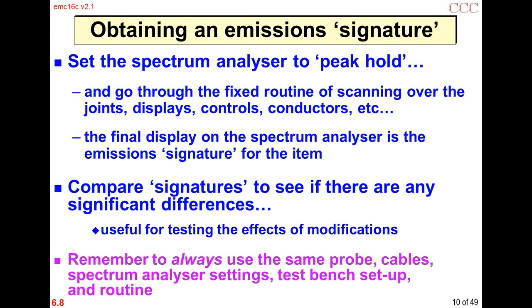But it's very important to always use exactly the same probe. And if you've dinged it, then it's no good. You've got to go get your signature again, because putting a bend in it or something will affect its performance. The same cables, the same spectrum analyzer, the same test bench setup, and of course the same procedure. It helps also to have a particular known source of noise, like your laptop, for instance. You might find that in a particular area of the touch pad, you can see noise on your close field probe, and so it's worthwhile checking that you just hold the probe by the touchpad in the right place and check that you get the same thing that you're used to seeing, because sometimes connectors, RF connectors can fail, for instance. I've seen that happen. And you spend a long time thinking, oh, we've made it really good, when in fact all it is the connector's broken.